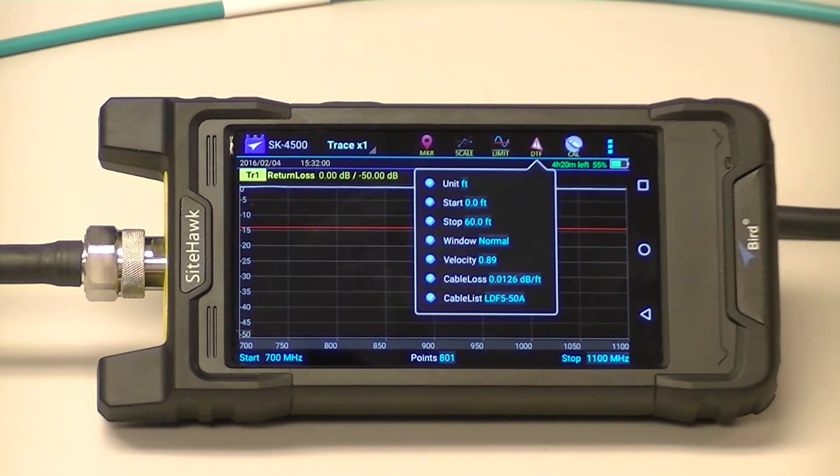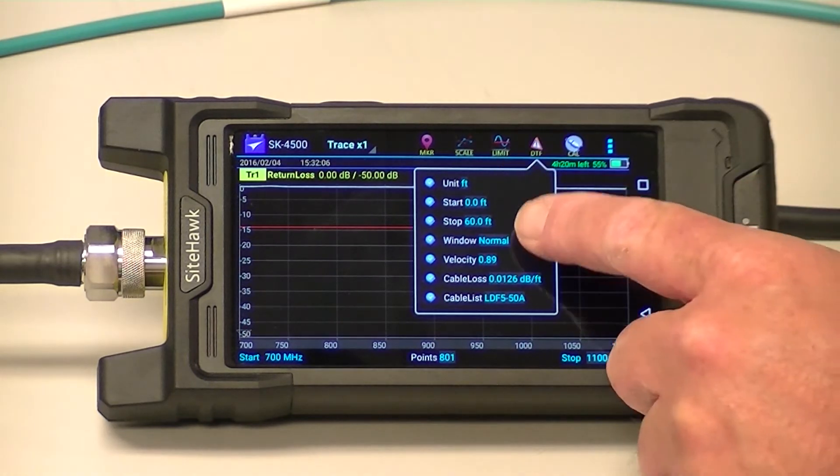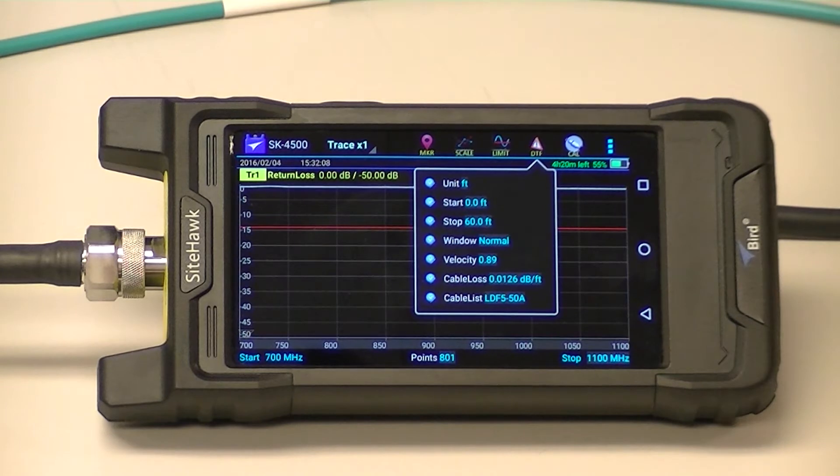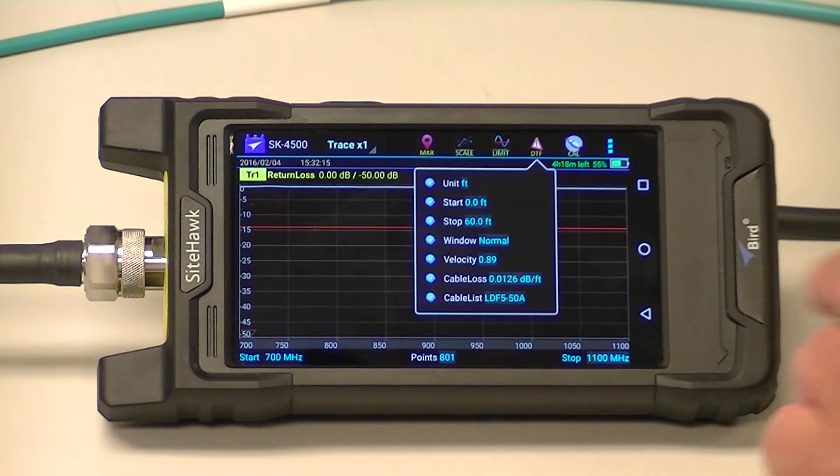If you're doing a distance to fault, you want to set up your DTF units. So my units are in feet, my stop distance is at 60 feet. I have my cable information selected from the cable list. I've selected LDF5-50A.